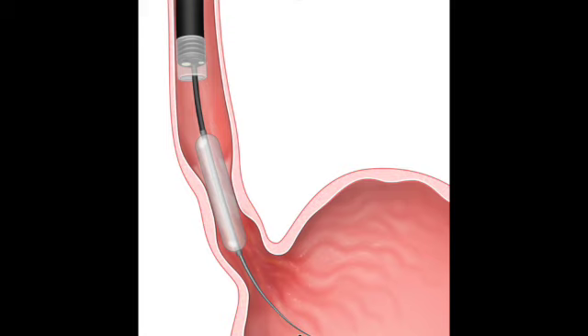Yeah, and the balloon is wrapped tightly around its catheter, but if there's even a microscopic trace of air left inside, the balloon material will not lay perfectly flush. Oh, it's going to bulge. It creates a tiny, almost invisible bulge. And in a channel that narrow, that microscopic bulge introduces fatal friction. So it would just get stuck. The catheter will simply jam halfway down the endoscope. So the assistant must pull that absolute vacuum so the balloon becomes as flat and rigid as a ribbon. It's a game of millimeters. The video even offers this highly practical, boots-on-the-ground medical hack for dealing with that friction, which I loved. Oh, the biopsy cap trick. Yeah.